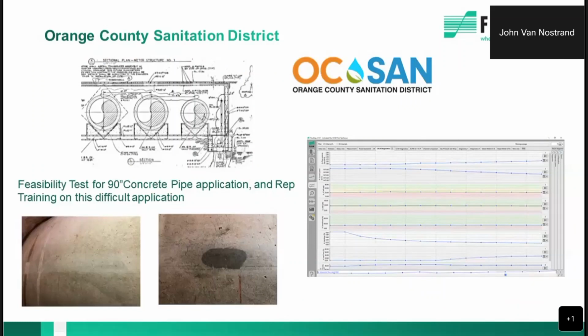Orange County Sanitation District, this is another concrete pipe, and I'm really focusing on concrete pipe for this application because when you think about it, you install a Magmeter in a concrete pipe, you're going to use that insert style. They're not very accurate, they're not very reliable, and if you install a full bore Magmeter, you're looking at some serious costs. What I'm asking you to do is have a look at FLEXIM, and we can do a feasibility test very, very quickly to go out and do an install and demonstrate the meter. There's no cost to you to do that, and we can then determine that it's a good application.